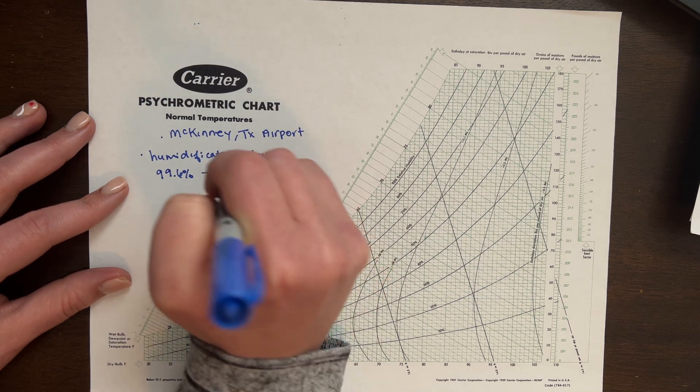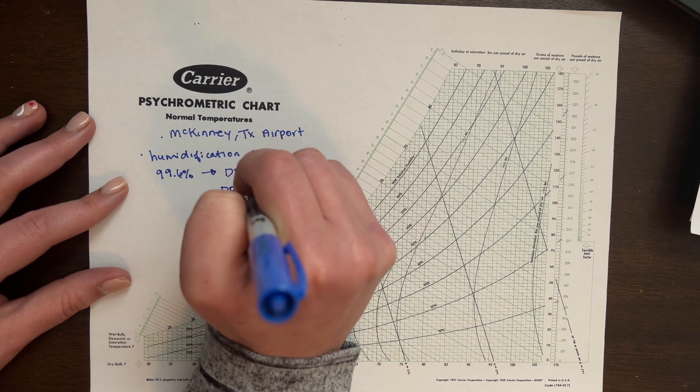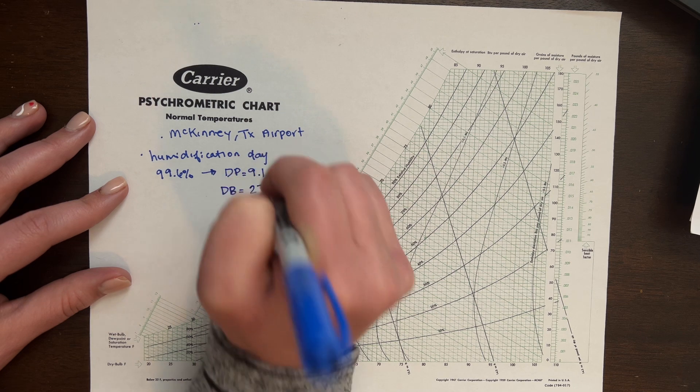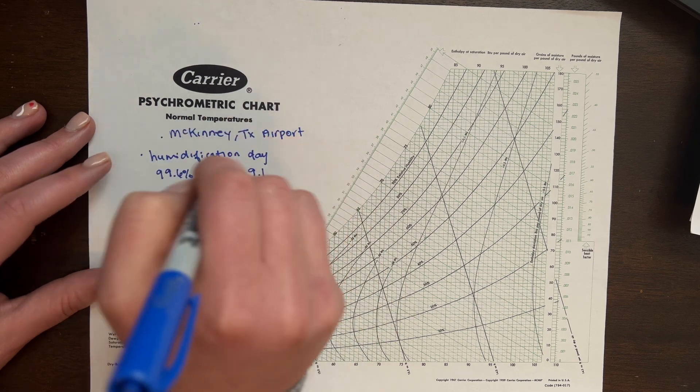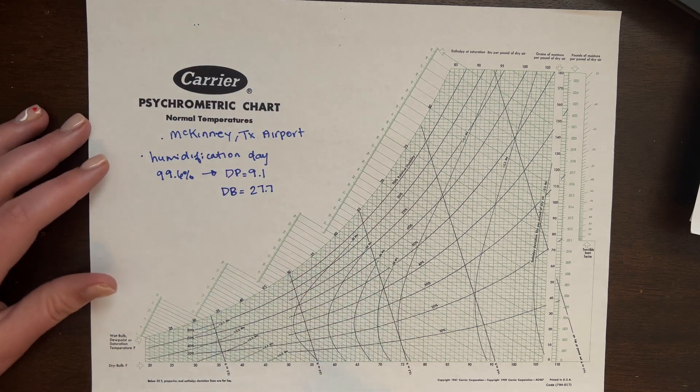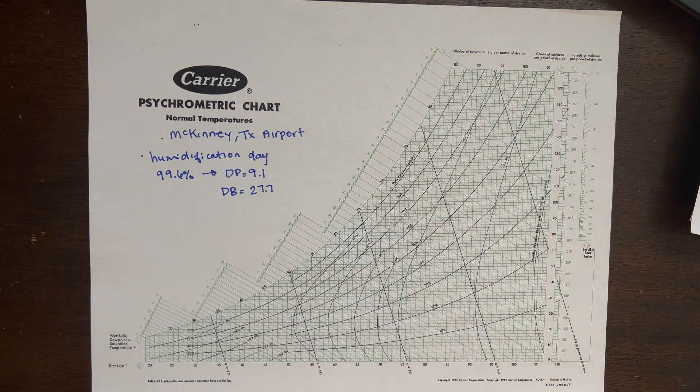And that gives us a dew point of 9.1, and it also gives us a dry bulb temperature of 27.7. Again, I got this from ASHRAE. You can get it from the 2021 ASHRAE Handbook Fundamentals. Okay, so then what does this information give us?